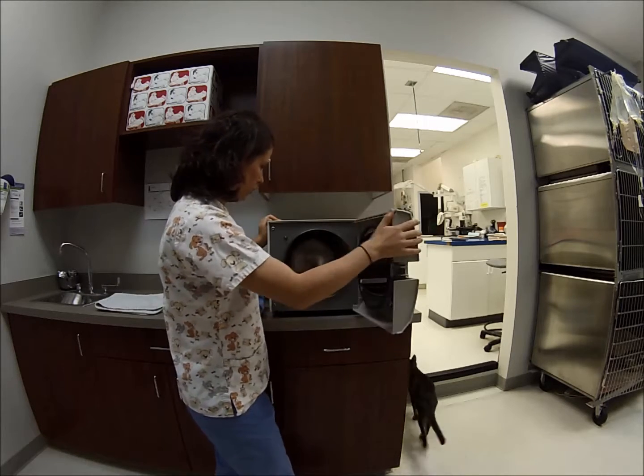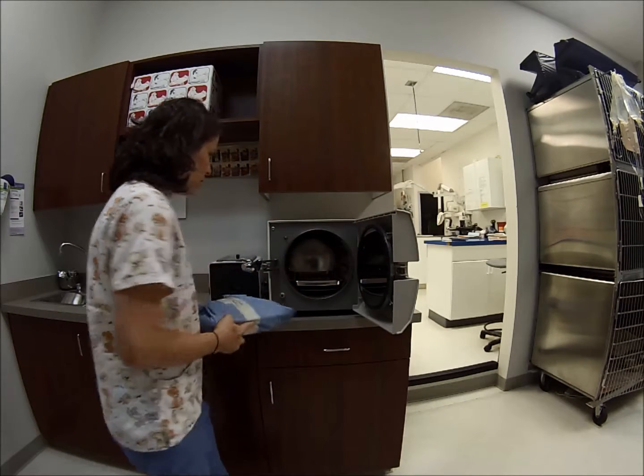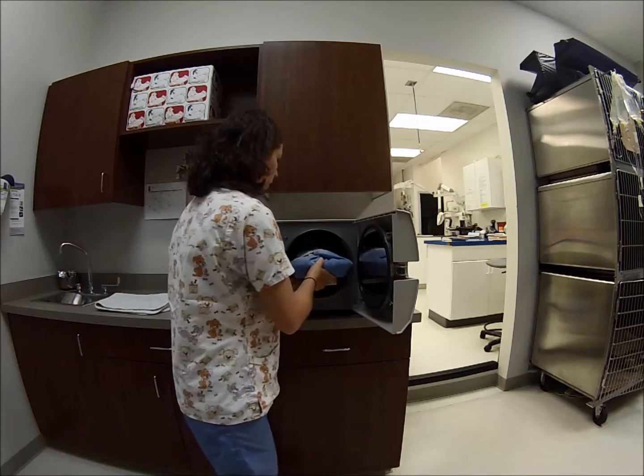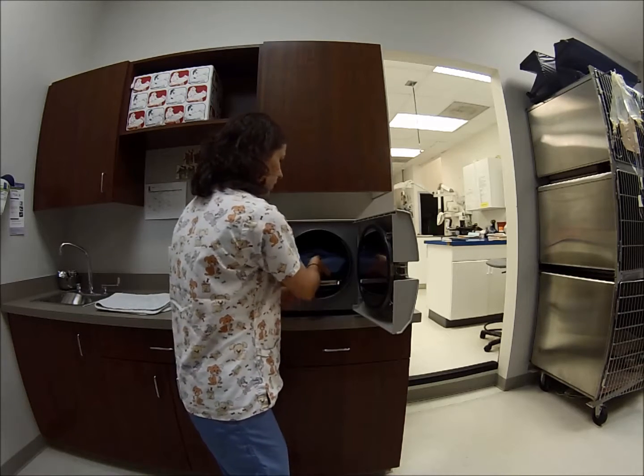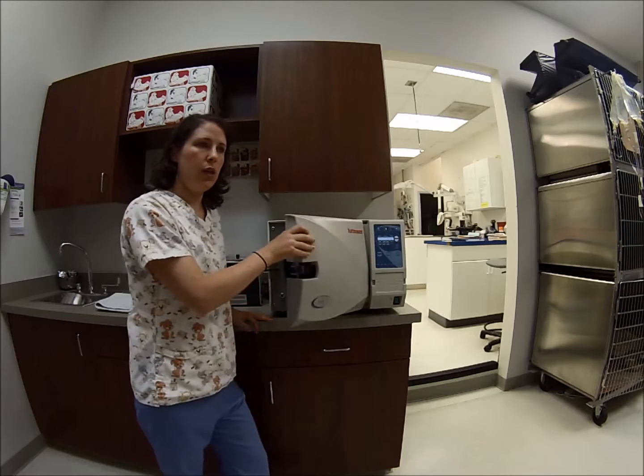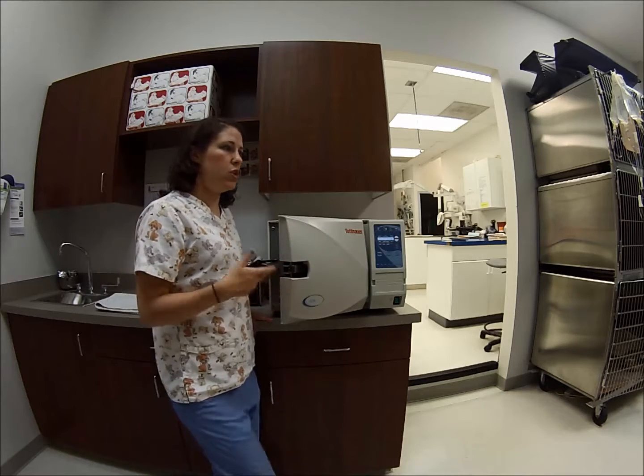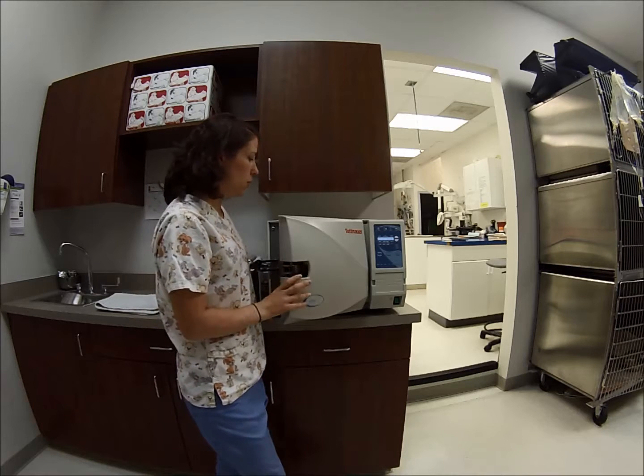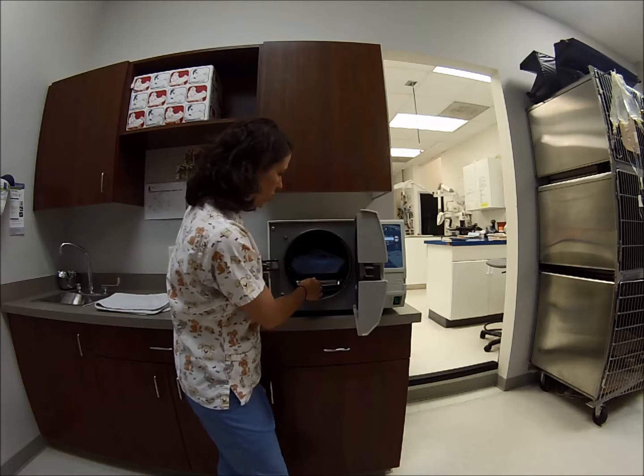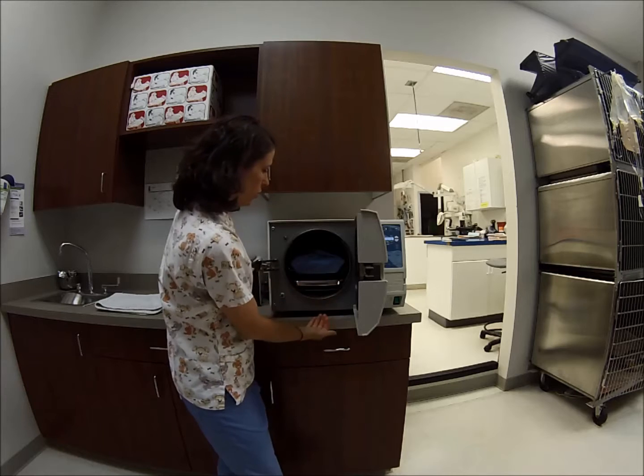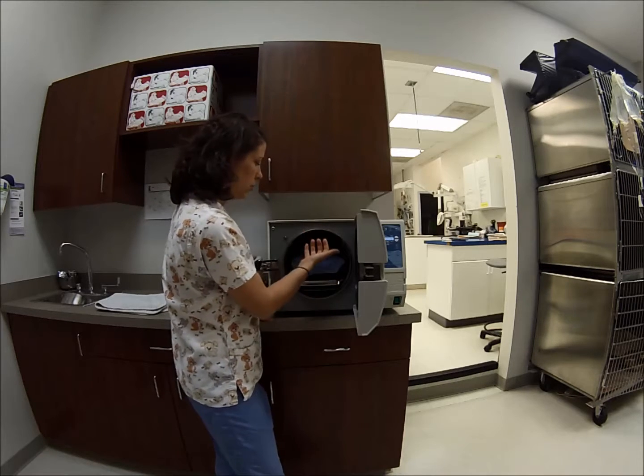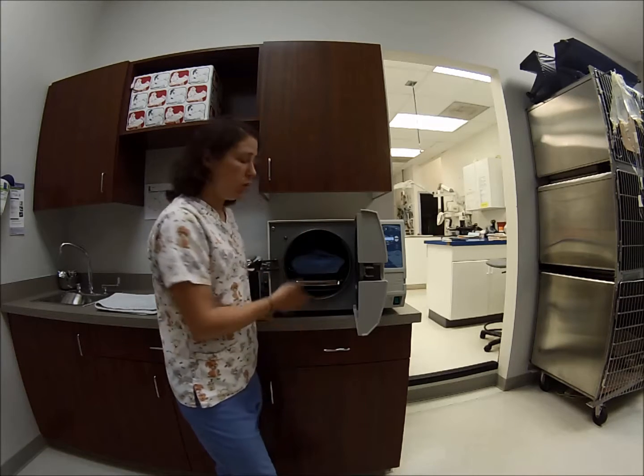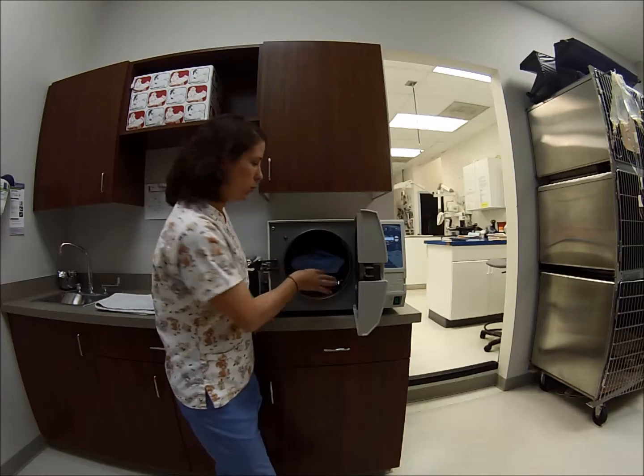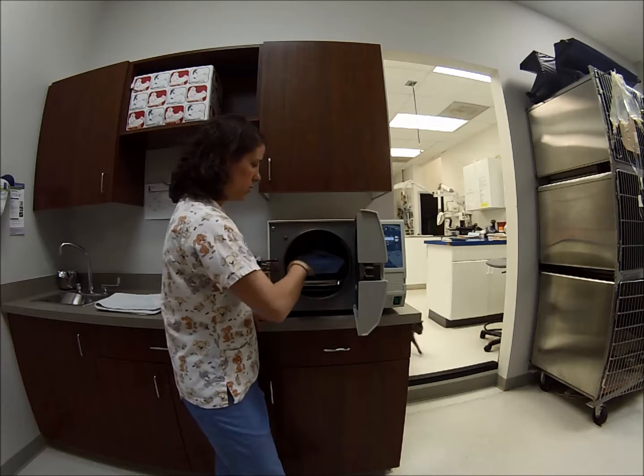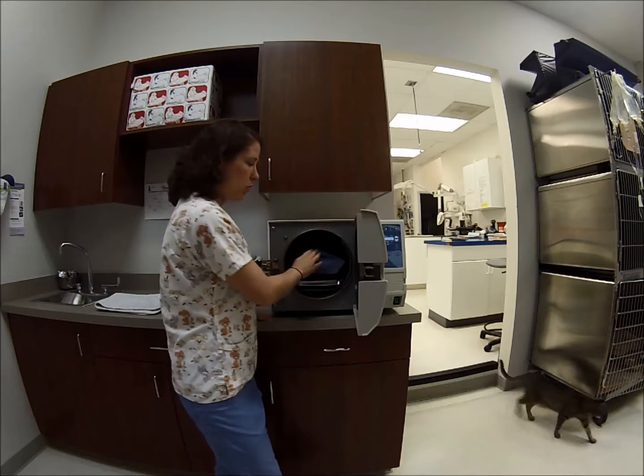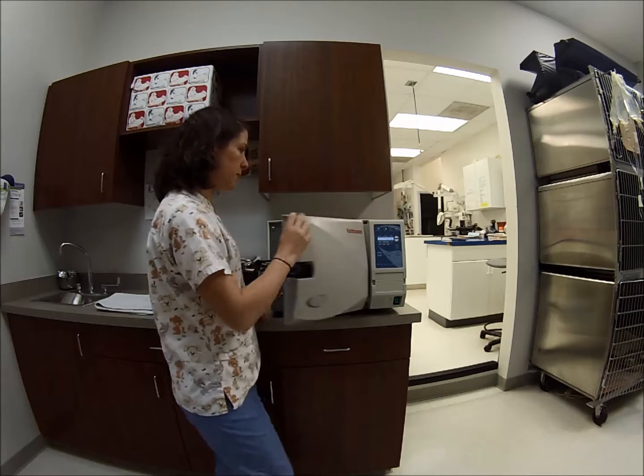So it's important when you're loading the pack to not overcrowd the autoclave, because if the autoclave is too crowded, then there won't be proper sterilization, there may be moisture buildup. So you always want to make sure there's not too much in here, there's room for the steam to kind of penetrate the packs. Make sure, if you're doing more than one pack, there's a couple inches in between. They're not stacked. So this pack's pretty large, so I'm just going to run this one pack here.